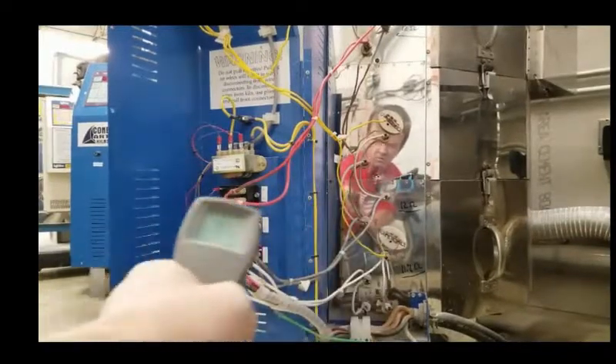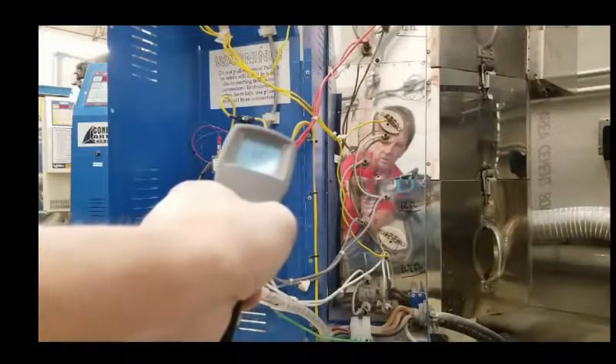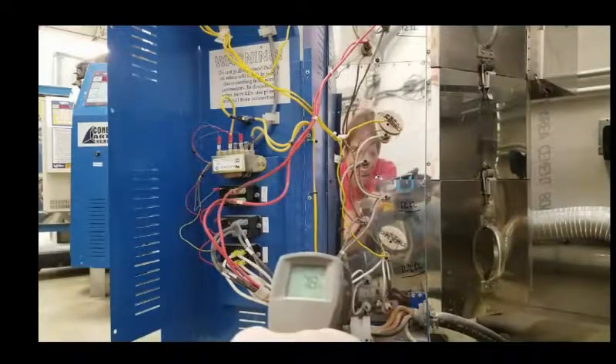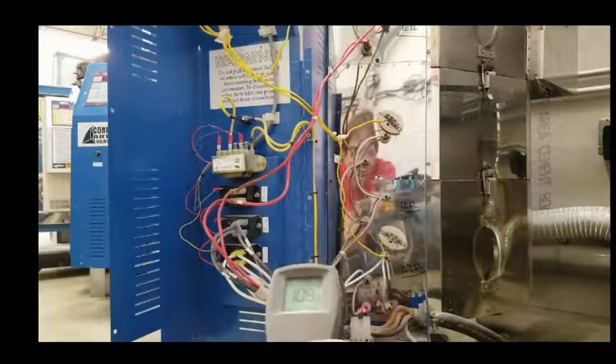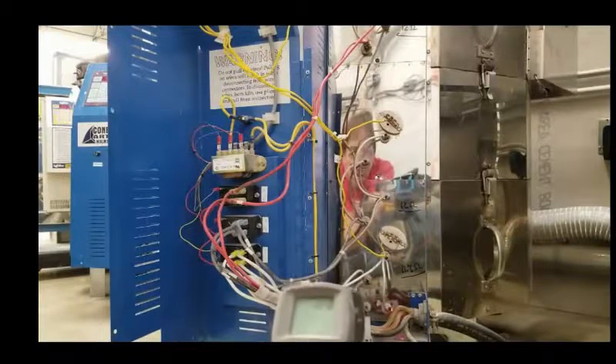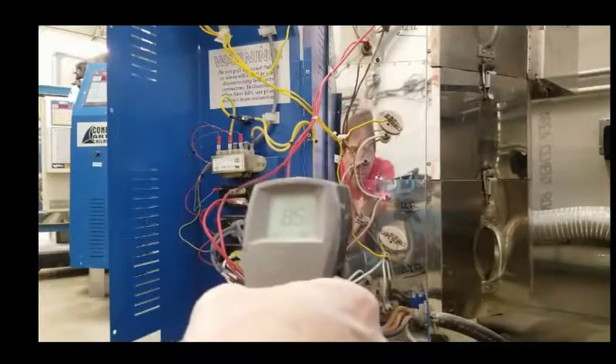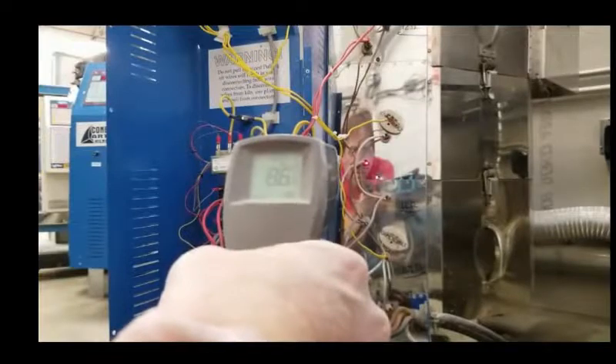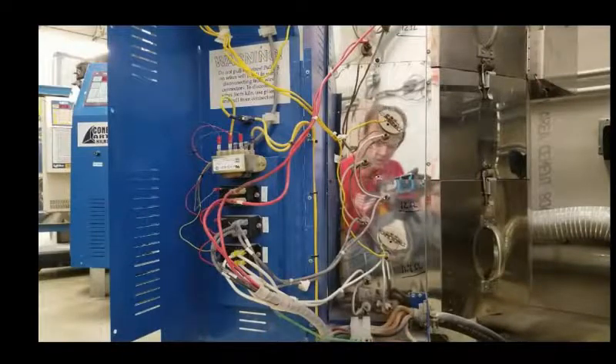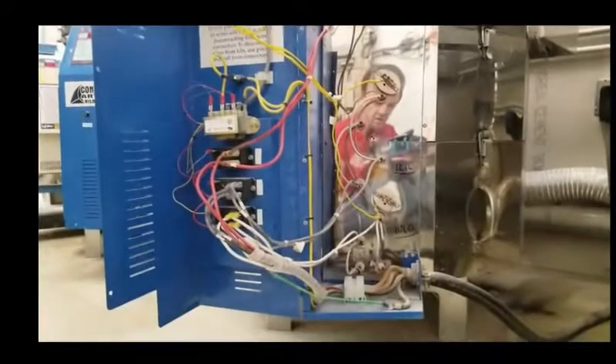So now we're going to try to get some advantageous point so you can watch. So again, nothing really crazy hot like 200 degrees. That connector down there, though, if I could hold this steady and stay behind the camera, doesn't look too bad. I got 140-ish out of it. So again, that's one we're going to check. The rest of these look good on the floor, and as I scan through them, they're pretty decent. 80, 90 degrees. So this bottom corner one is 130, 140. I'm going to guess that that is loose and corroded a little bit. So it's hotter than the rest.